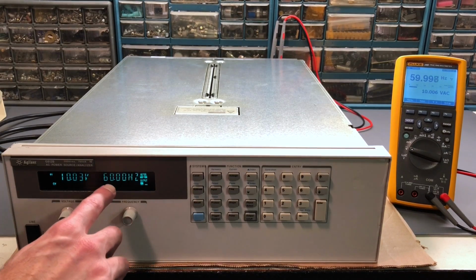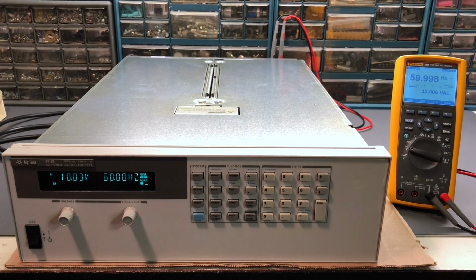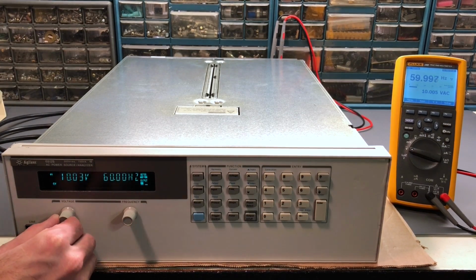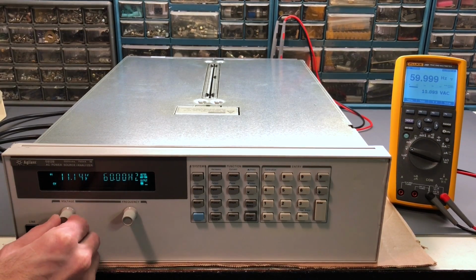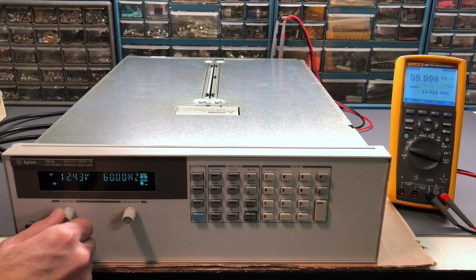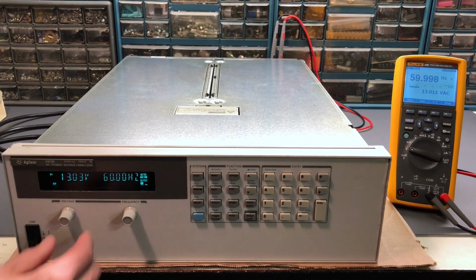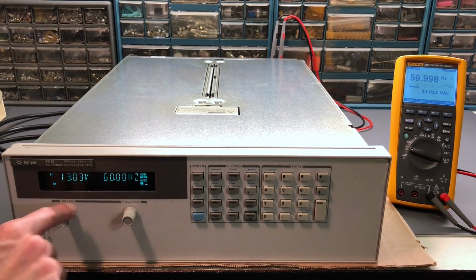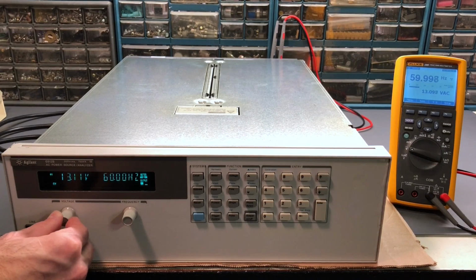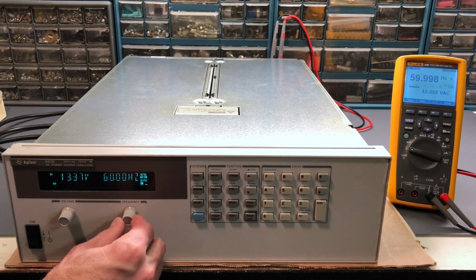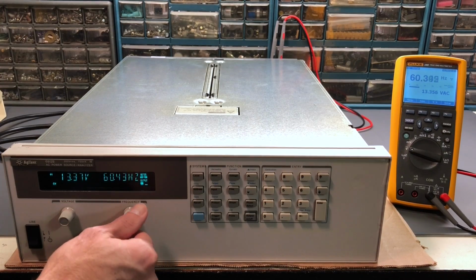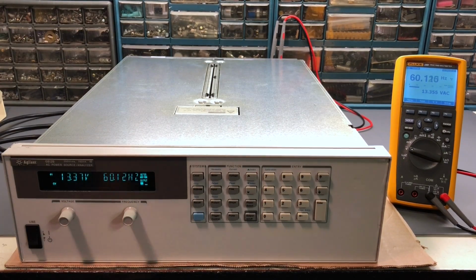And the frequency is set to 60 hertz. And that's what it's showing over on the display on the digital multimeter, 59.998. So right at 60 hertz, that's looking really good. So if I come over here and I try this voltage control, yep, that works. So as I rotate that, that's increasing the voltage. Now it's a little over 12, there's 13 volts, 13.03. Digital multimeter is agreeing with that, no problem there. Again, this was that rotary control that was so loose, so it is working okay. I change the frequency, yep, the frequency goes up. Frequency can shift down, no problem there.